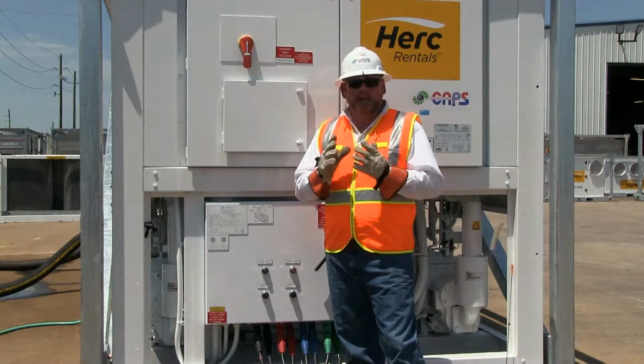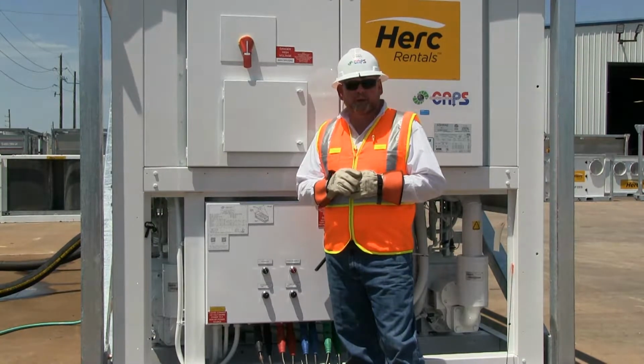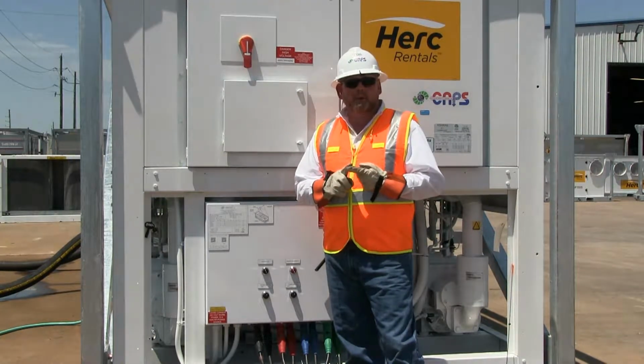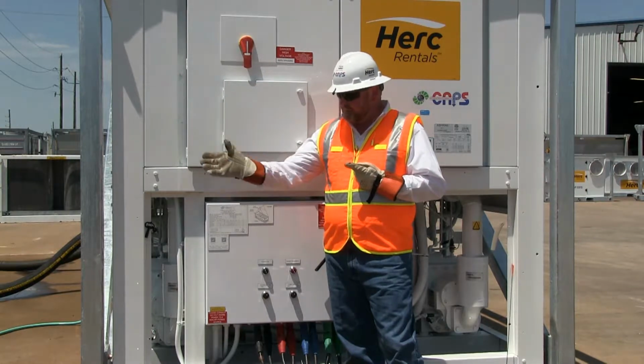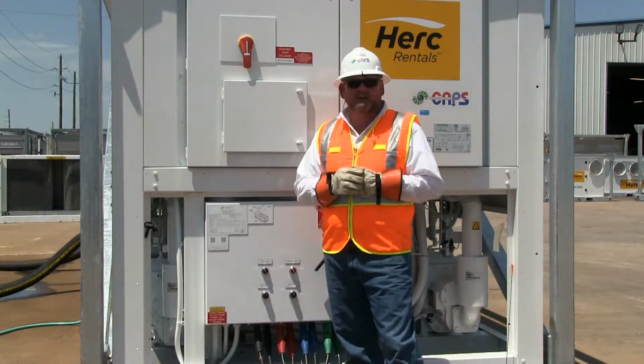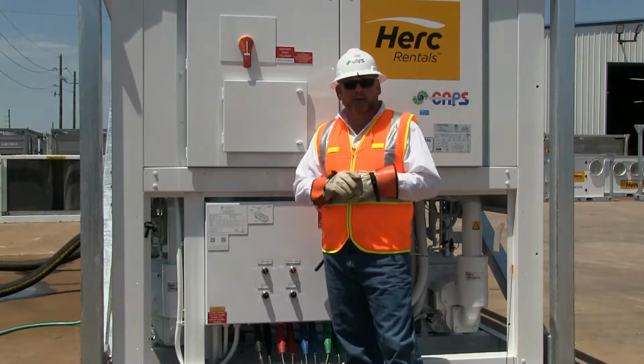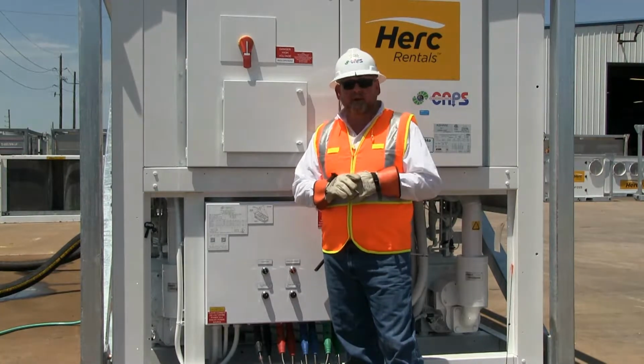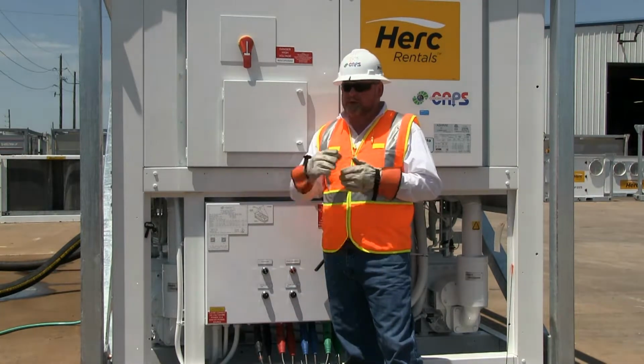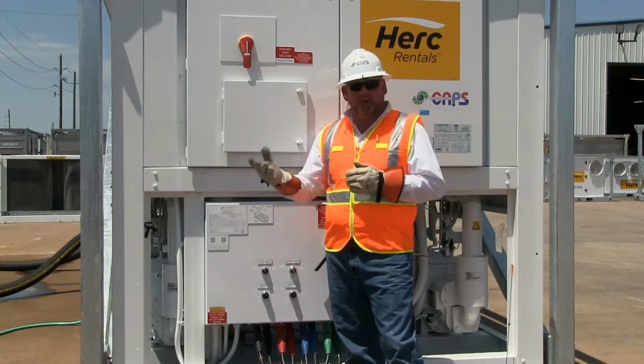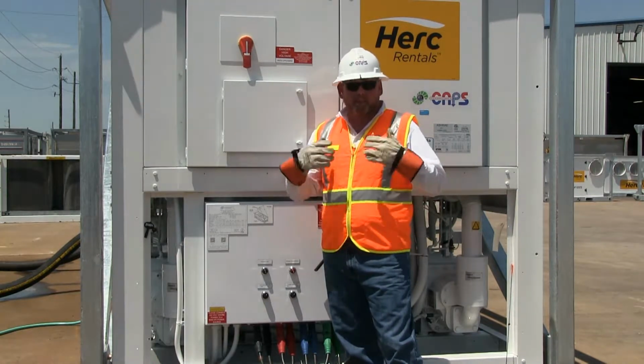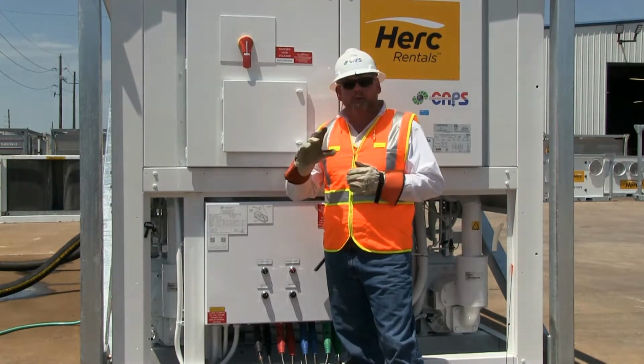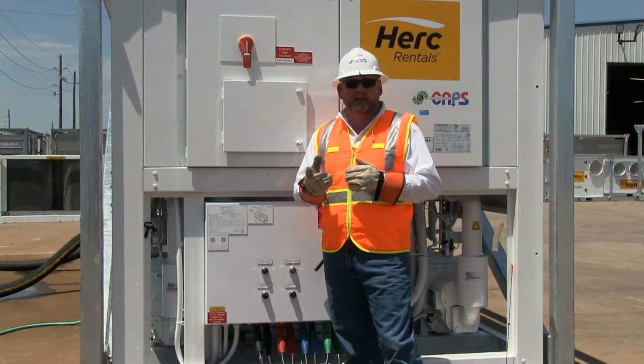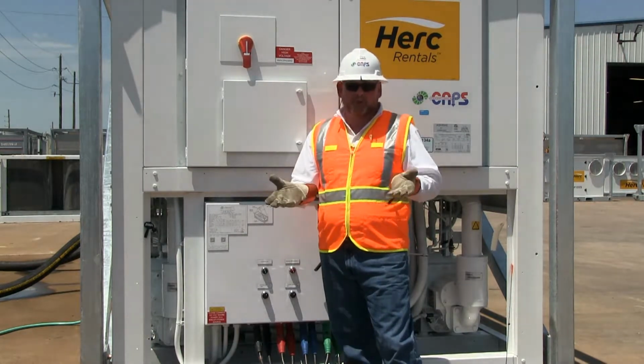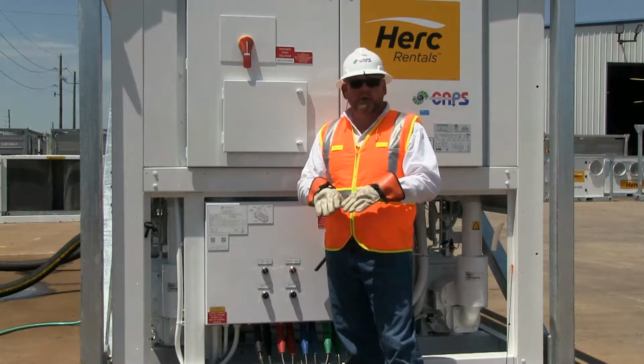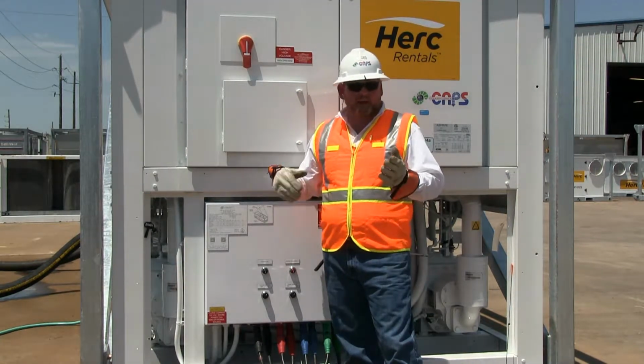Okay, just to recap the installation of the 200-ton air-cooled chiller, we verified our power requirements and have enough power coming to the machine, which is 379 amps. We've set the machine on good stable ground using a forklift. We've plumbed in the system with 4-inch Camlock fittings. We filled the system completely up with water, bled the air out of the system. We've cycled our pump several times to stir the water, push the air to the high points, water down to the low points. Now we've got all the air out.